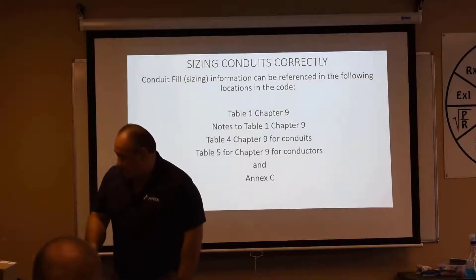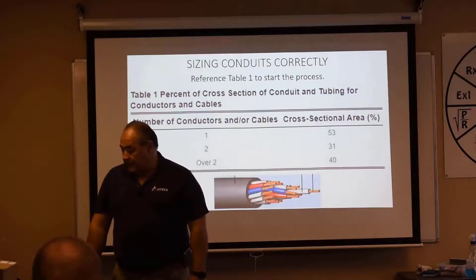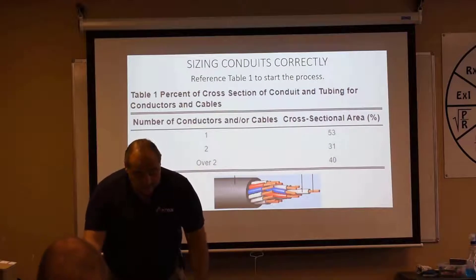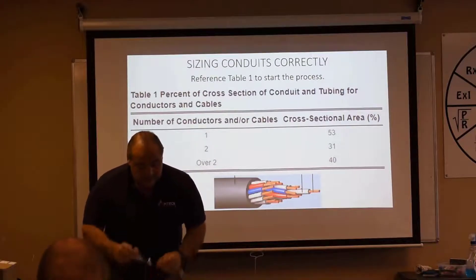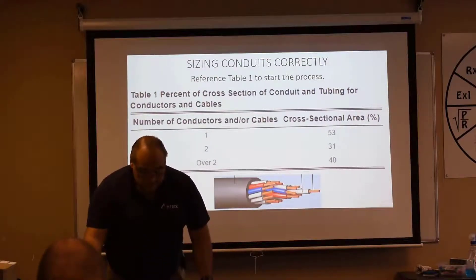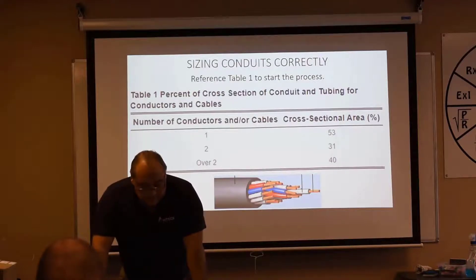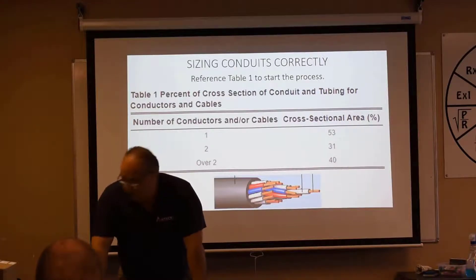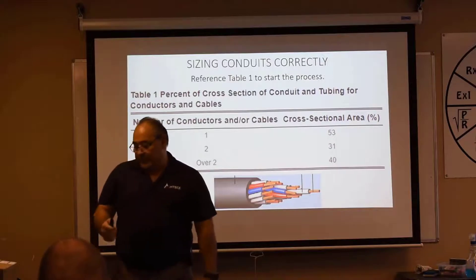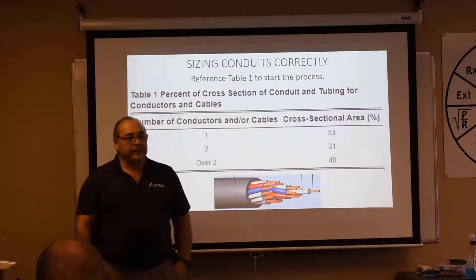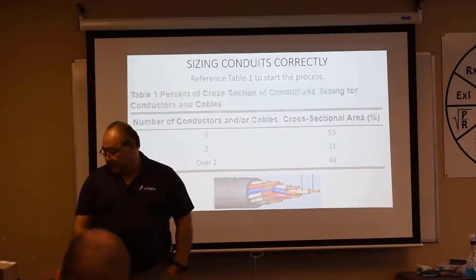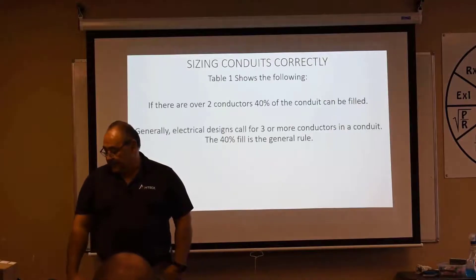Let's look at Table 1, Chapter 9. It shows percent of cross-section of conduit and tubing for conductors and cables. We have number of conductors and/or cables: 1, 2, and over 2. Then we've got cross-section area and percentage: 53, 31, 40. I want you to draw a percentage sign there so you know those are percentages.